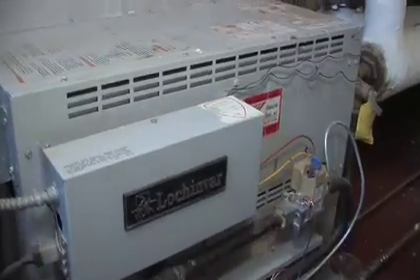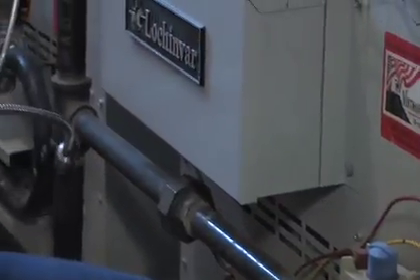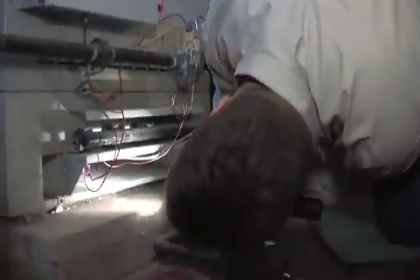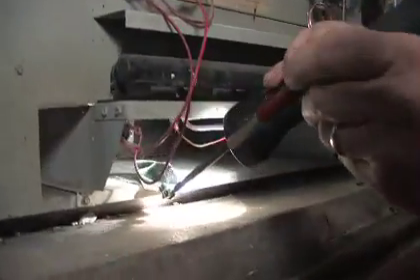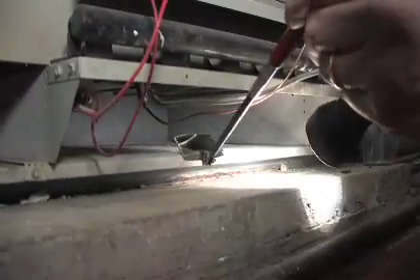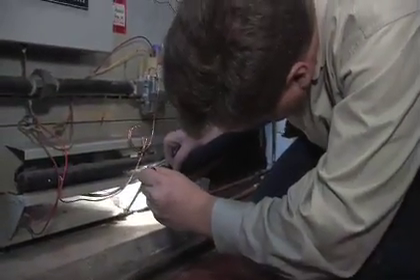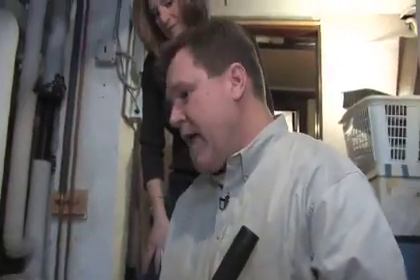So what would you do first? This boiler is a fairly sealed system, so there's not a whole lot we're going to be able to look at, but we do want to get a look at the controls for it, look in the burners. I'm going to test for gas leak, test for carbon monoxide leaks, just make sure the systems are operating properly. Okay. First thing we're going to do is look down in the burner area. As I said, this is a pretty sealed system, so there is not going to be a whole lot that we can inspect. But I do want to see, in this case it's running right now, so there's flames on, and I want to be able to look in there and see if there's any blockage, any leakage, anything like that happening in here.